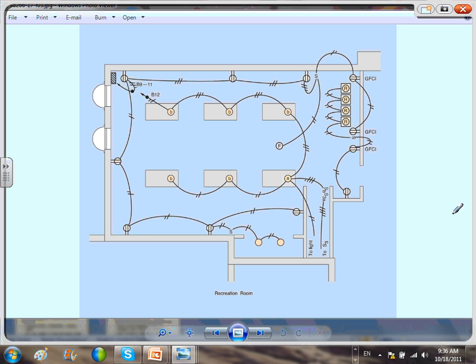They brought one circuit here. If you guys can see, this circuit is feeding all these recessed lay-in, they call them lay-in, exactly like above your head, recessed lay-in fluorescent lights, 2x4 lay-in fluorescent lights. You set them right in the grid because they have a grid there. And they bring it to a J-box and you loop it with a fixture whip. So they brought the circuit here, guys, and you feed all these, and then they came up with a dimmer right here to dim all these lights, and I think there's another light that's going somewhere else, the other way. So that's one circuit to feed all the lights. So that circuit is feeding each and every one of these lights through a dimmer.